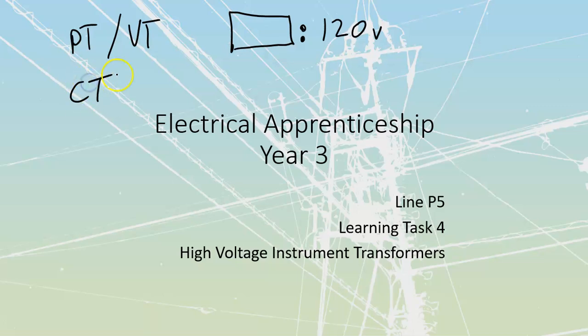Our CTs are also going to have a standardized secondary, and the standardized secondary is going to be 5 amps. And once again, whatever we've got for a primary side that we're going to be feeding in is going to get placed inside there. It might be 300 amps to 5, it might be 800, whatever it is, based upon the size of the system itself. There are going to be standard sizes inside here. You're not going to have oddball sizes.